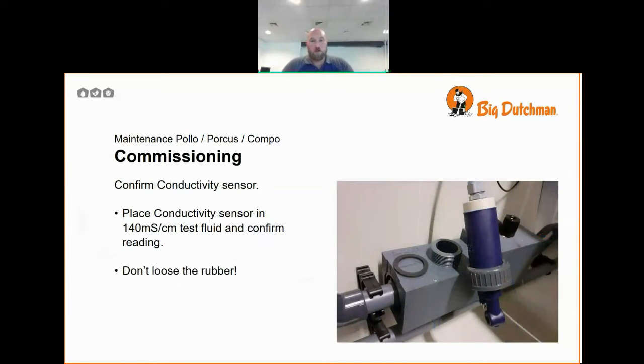We also need to place the conductivity sensor in a test fluid of at least 140 millisiemens and confirm the reading. Whenever removing the conductivity sensor, take care not to lose the rubber seal.